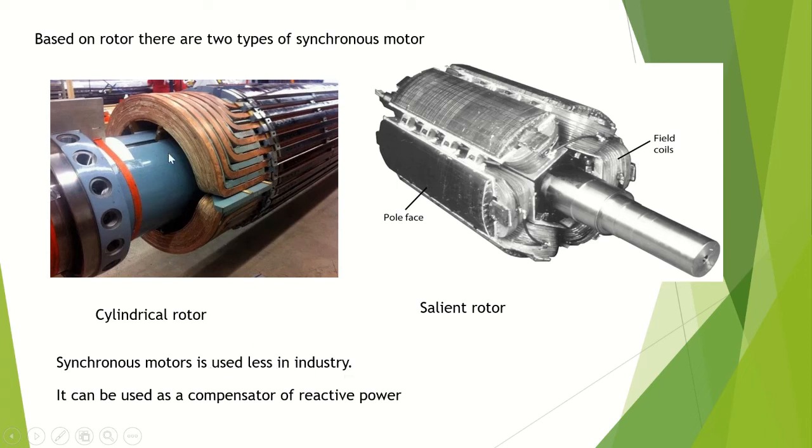This synchronous motor can also be used as a reactive power compensation device, because you can control the excitation in the synchronous motor. By controlling the excitation, you can operate it as a reactive power compensator. In the overexcited state, it will act as a capacitor and it will deliver reactive power to the system also.